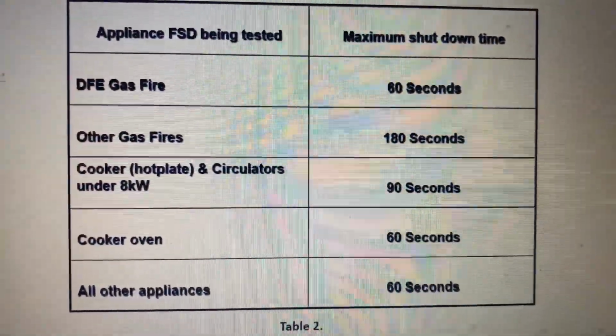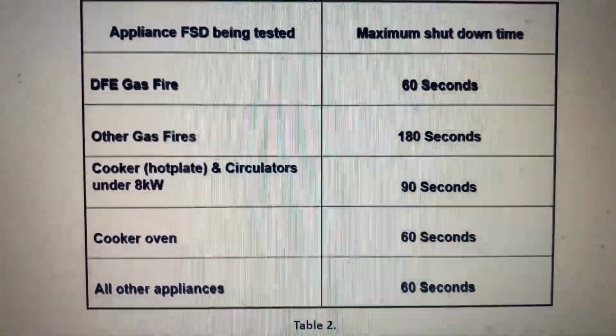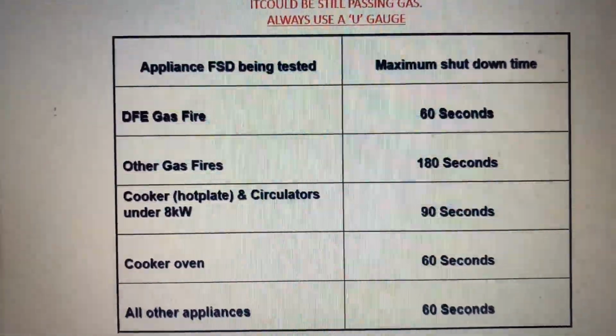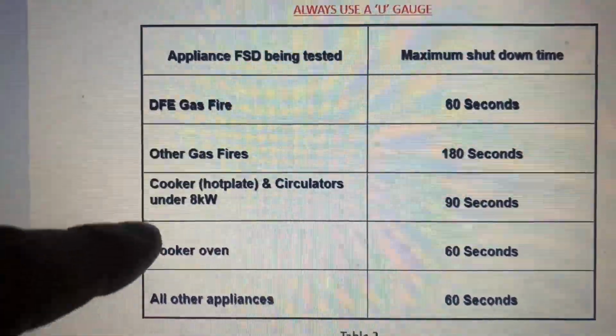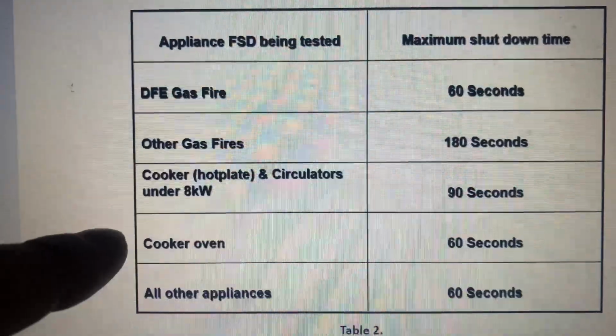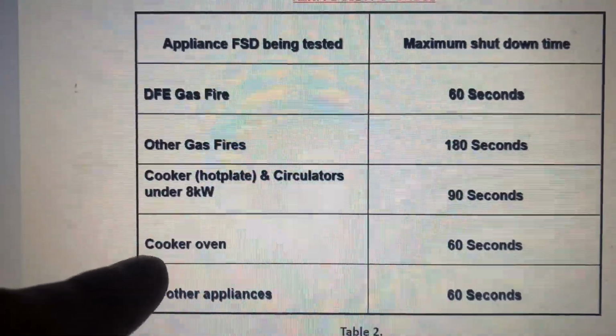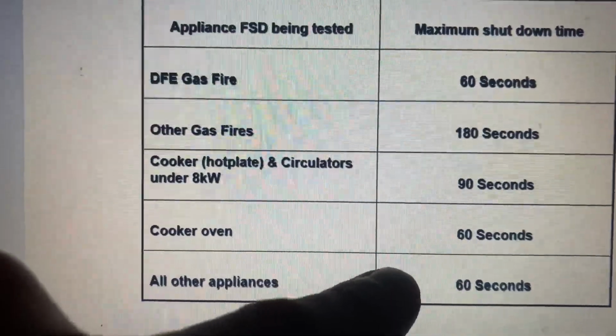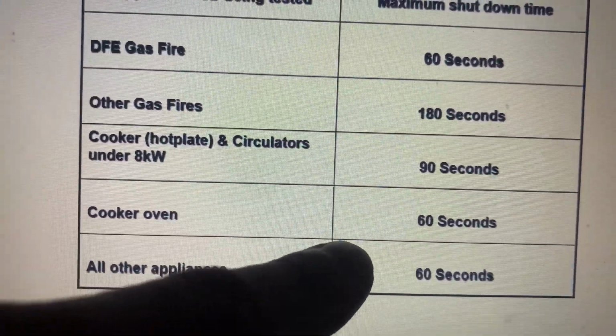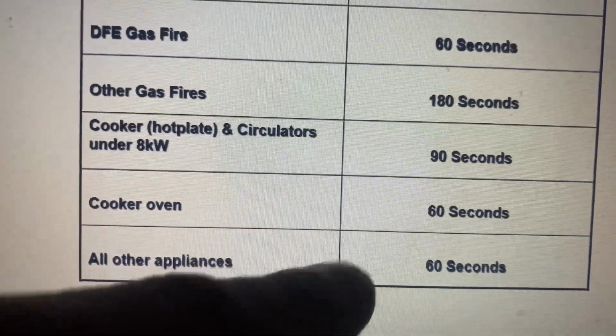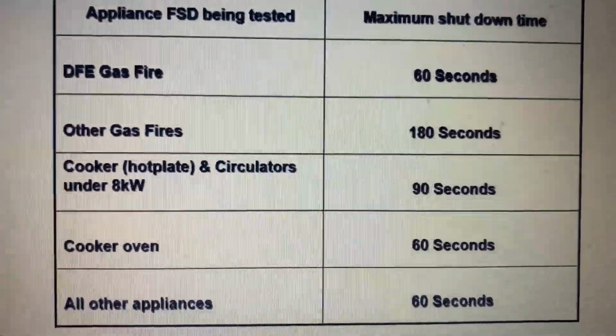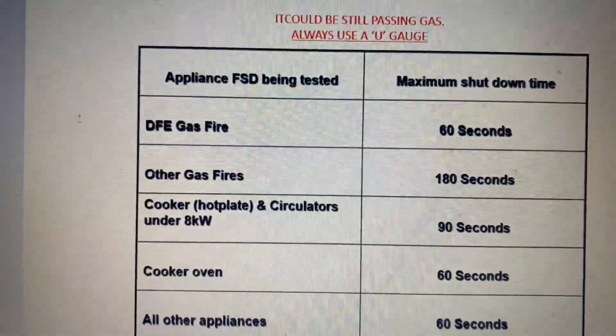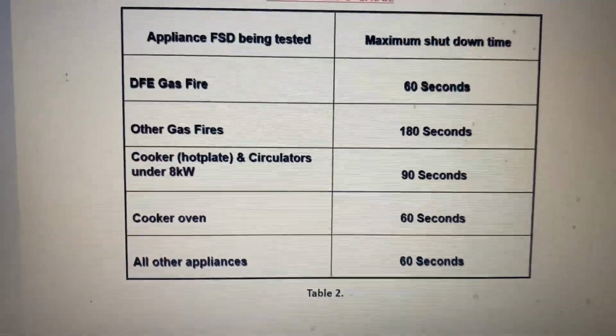So this might seem a little bit complicated now. So if you were to blow your flame out, the burner out, this is how long it should take to shut off. So, for example here, your oven, within 60 seconds, the main burner should switch off through the flame safety device. But however, remember the cooker is dangerous because the bypass will still actually let a small amount of gas through. Another check, put a piece of paper in the oven door, close it. If it drops out, the seal's gone on the door, it's letting out too much heat.